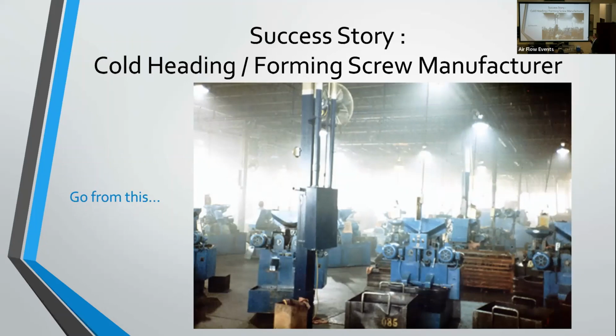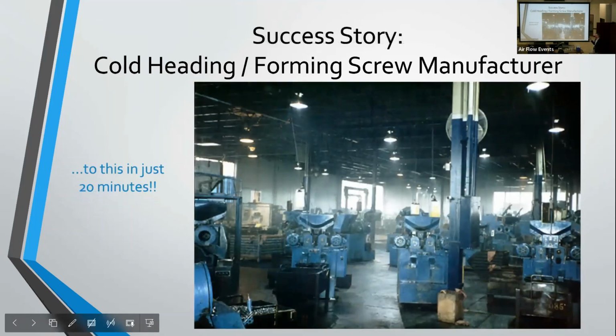So what happened is they shut the general exhaust fans off. They got the makeup air units installed, got the makeup air units on, and then 20 minutes later went from this to this, which still isn't that great of a quality of a picture. But you can see just in 20 minutes that it clears up that space, and you can actually see these pillars, you can actually see these doorways. Just at 20 minutes at 3 air changes per hour.